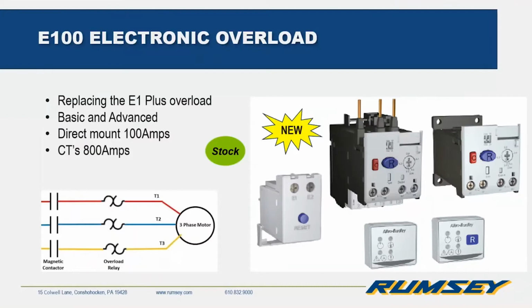So the E100 will be the overload going forward, and it mounts to the same 100C contactors that the E1 Plus mounts directly to. They are both the same physical size as well, so it should be an easy swap. One of the differences in the new E100 is that the same unit can be used for single phase or three phase applications, where the E1 Plus had two different units for that. The E100 comes in two versions, a basic and an advanced. The basic will do 90–95% of applications. It has two trip classes, 10 and 20. It is only a manual reset, but again, this will be used most of the time.